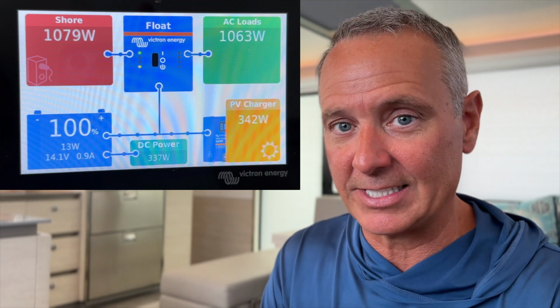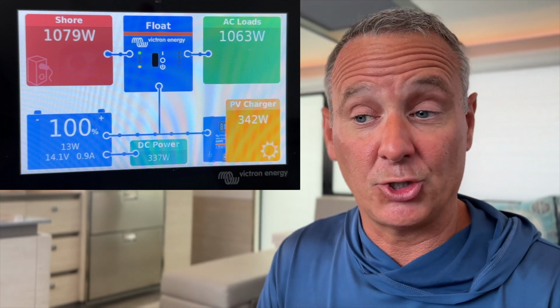So it's 60 watts when it's doing absolutely nothing. Then when I turn on the AC chiller breaker, the water pumps fire up after a few seconds before the compressor turns on - there's about 30 to maybe 60 seconds before that. That's where I took that reading of roughly 1,060 watts, which should be just the draw from those water pumps, the two Calpeda pumps. So 1,060 minus the 60 with nothing running nets me roughly 1,000 watts to run those two pumps.